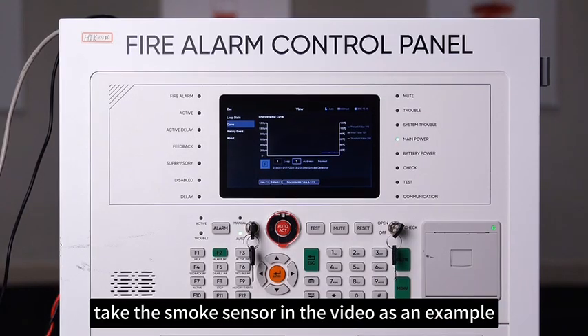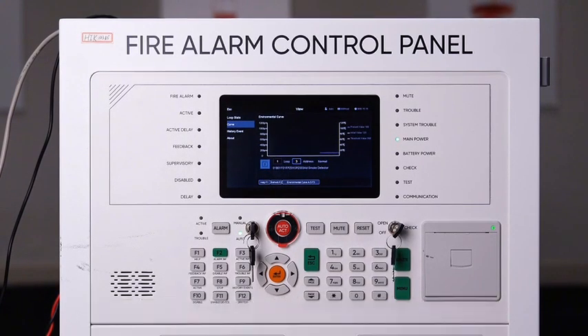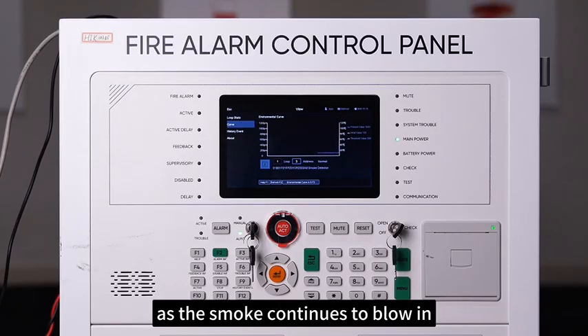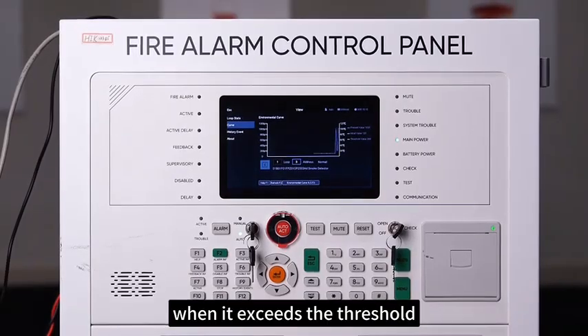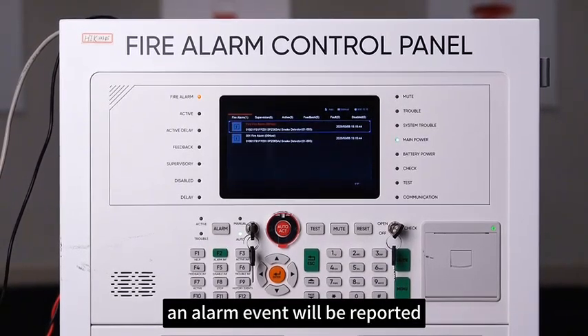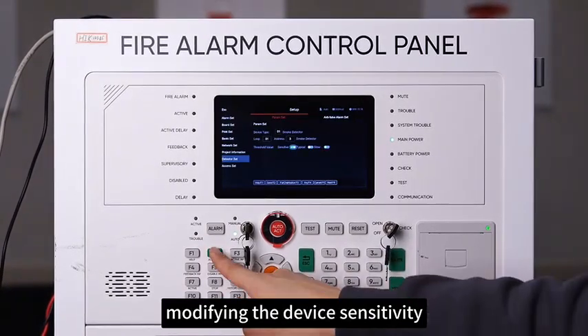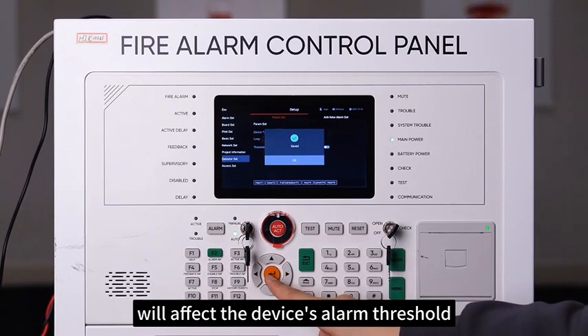Take the smoke sensor in the video as an example. As the smoke continues to blow in, the current value continues to rise. When it exceeds the threshold, an alarm event will be reported. Modifying the device sensitivity will affect the device's alarm threshold.